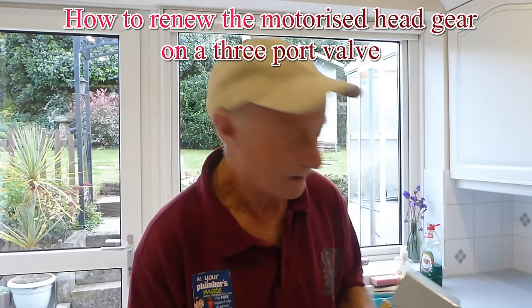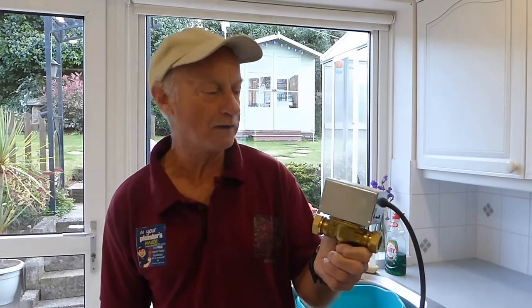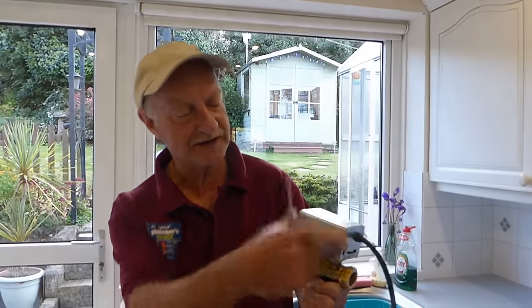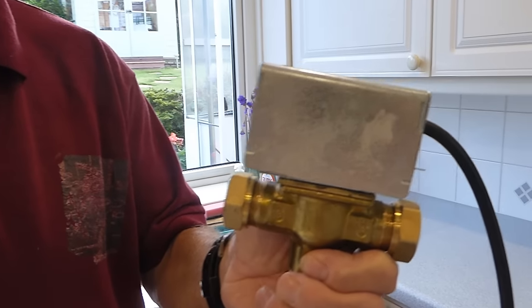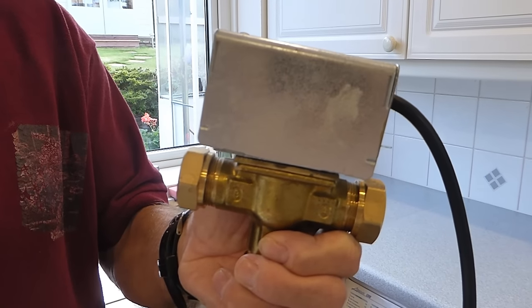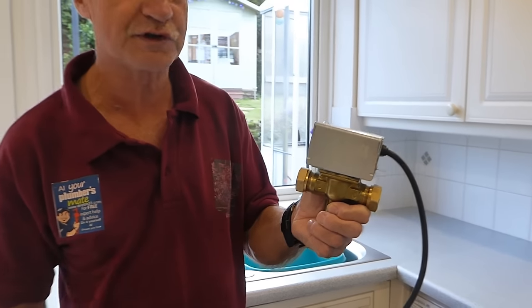Hi everyone, welcome. Today I'm going to show you how to renew the head on a three port valve. This is the most popular Honeywell one — it's a sprung return mid-position valve. I'm going to show you how to easily take that off and renew it. Personally I like to renew the whole valve when they go, but you can just do the head, and obviously it's a cheaper option and it saves you draining the whole system down.